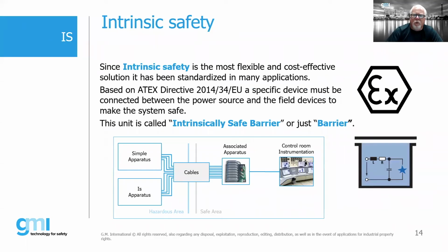So obviously we're here talking about intrinsic safety, although I think we have some questions about some other protection techniques that if we have some time, we'll spend some time on. But intrinsic safety is one of the most flexible and cost-effective solutions, and it has been around for many, many years. The original IS devices were developed in the mining industry back in the early 1900s for signaling devices. And under the ATEX directive, a specified device must be connected between the power source and the field device to make the system safe. So this unit is called an intrinsically safe barrier or just barrier.